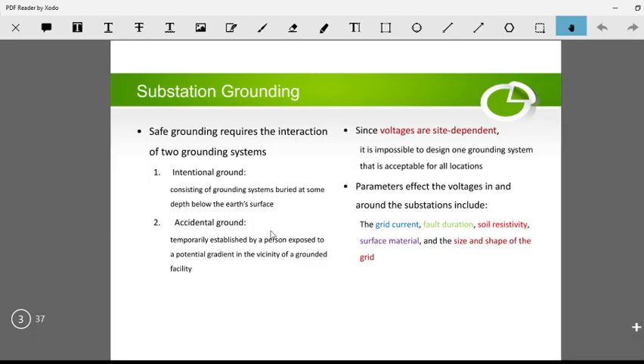We have to make sure that when accidental grounding happens, it will not harm the person who creates it. Because these voltages depend on the substation and the site, it's not easy to design one grounding system acceptable for all locations. You have to be specific to the location, since the grounding system depends on the area and the soil type of the ground where the substation is established.